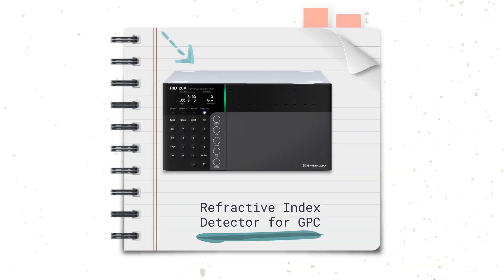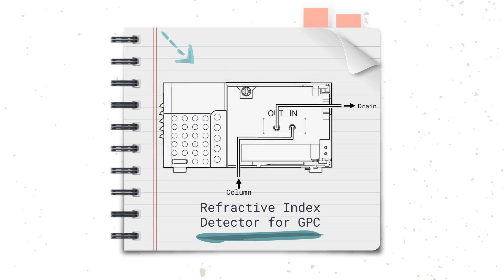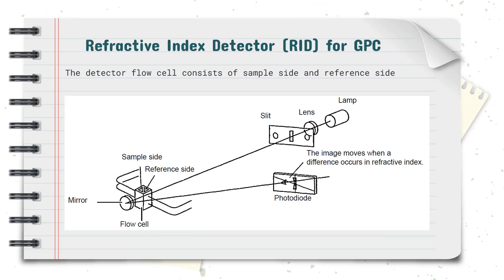The second component of GPC is the detector. One of the most commonly used detectors is the refractive index detector, or RID for short, and it's used to detect analytes when they elute out of the GPC column. The RID contains a flow cell made up of the sample and reference side, both of which contain the mobile phase. A light beam from the lamp inside the RID passes through both sides of the flow cell before being reflected on a mirror, creating an image on the photodiode.